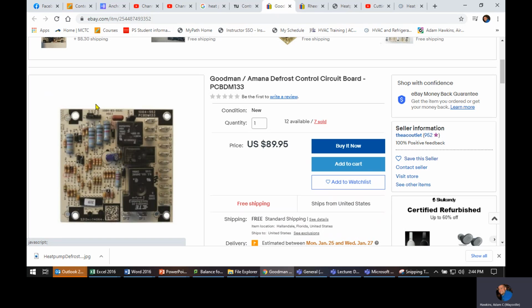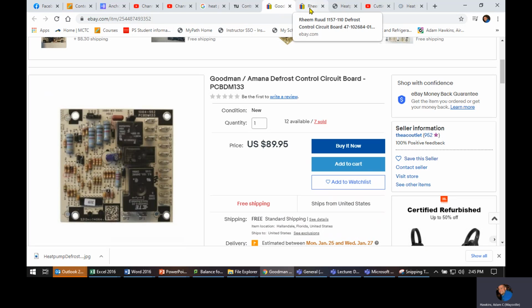Here's your 30, 60, and 90 over here, and your test. And here's your DF1 and DF2, which is your condenser fan cutout. So that's the ones we're going to work with in class. So hopefully that helps you on that, gives you a little bit of an idea on the electrical side about what's going to happen. So just to review, what happens when it goes into defrost electrically?